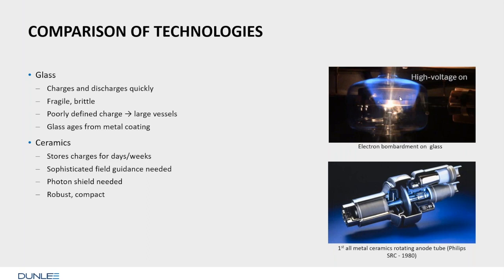So if a glass tube is in heavy ion bombardment and electron bombardment, the glass is subject to currents, and that's not good because the glass is not very stable. It is brittle, it is fragile, and if current flows over glass, it may break and implode. The other thing is that glass charges are poorly defined. They can turn from very positive to very negative, depending on the events. So you always need a surrounding environment, the casing, far away, to be prepared for all these situations. So you need a large tube housing to house a glass tube.